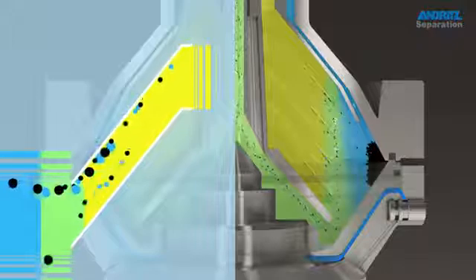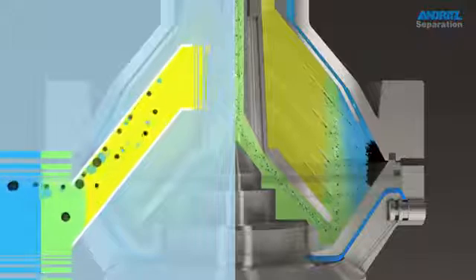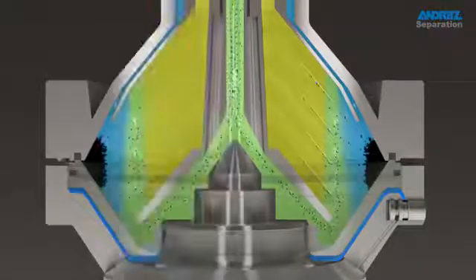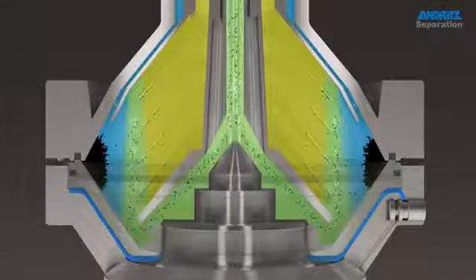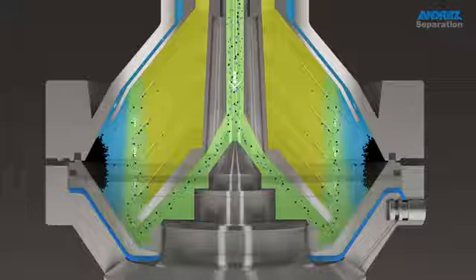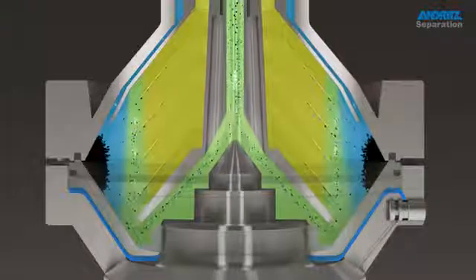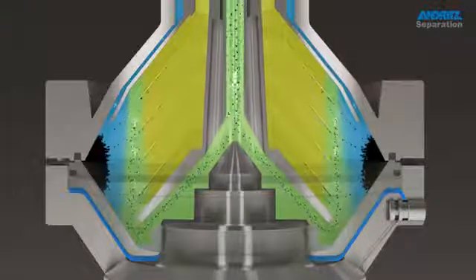While the contaminants reach the lower surface, they start to slide outward to the periphery, where the sludge chamber is. Separation takes place inside the bowl as a result of centrifugal force and the different specific weights.